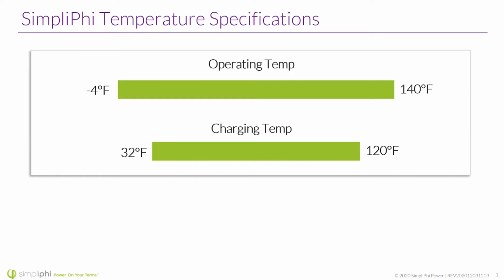And actually, before I go on, just for anyone that's working in Celsius, the charging temperature is 0 degrees Celsius to 49 degrees Celsius. So basically, the difference between operating and charging, operating being the battery's either in a discharge or that it might be in a standby mode. So that's operating. So for the most part, we typically need to consider charging temperature as the more important of the two. And that's our window we want to sit between 32 degrees Fahrenheit and 120.